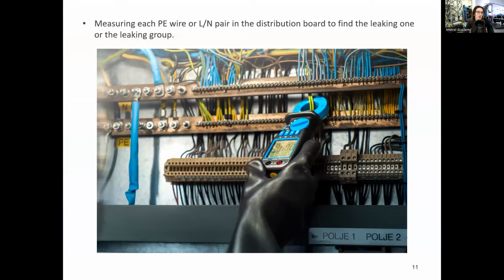Our next application is essentially the same thing that I showed you in the schematic form earlier. We are looking for the part of the installation that is leaking, using the connections of protective earth to the common bus bar. It is possible to clamp multiple wires at the same time, which will help us work faster. And once we see leakage in a group, then we can look at each wire separately to finally find our source of the leakage current.